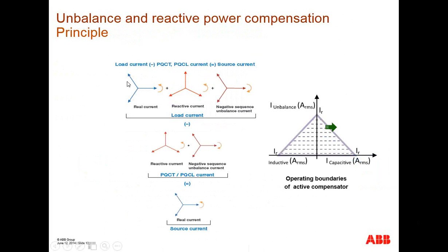You can see here the load current, which consists of active current, reactive current, and negative sequence, which is causing the unbalance. What the active compensator does basically is subtract the complete reactive power as well as the negative sequence. So after subtracting this reactive power and negative sequence, only the balanced active current is drawn from the distribution transformer. So it has three directions. It can go 0 to 100% capacitive, or 0 to 100% inductive, and it can also go 0 to 100% unbalanced compensation.